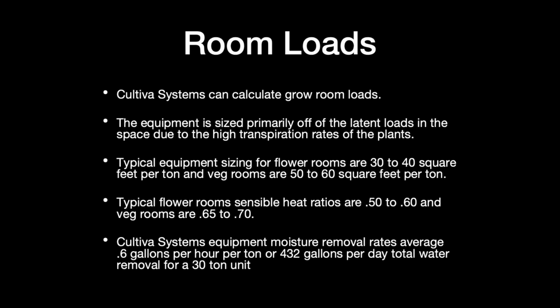Your equipment is going to be sized primarily on latent loads. The latent loads really dominate, particularly in the flower or bloom rooms. In the veg and the clone rooms, the latent load is not quite as dominant, but in those rooms, you've got to make sure that you've got enough auxiliary heat available, because you are going to have to remove the moisture, and if you can't reheat that air back up, you're going to overchill the plants.